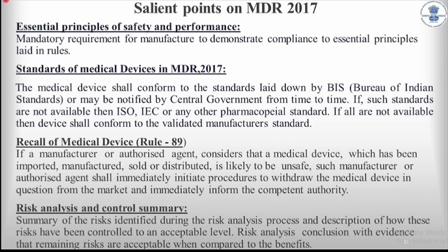Risk identification and risk control strategies are a continuous process, and as and when there are more and more adverse events or more and more literature, even on their product or on products in the market working on the same working principles, every manufacturer or company is required to look into their risk analysis document, improve their risk analysis and make efforts to reduce the risk to the minimal point.